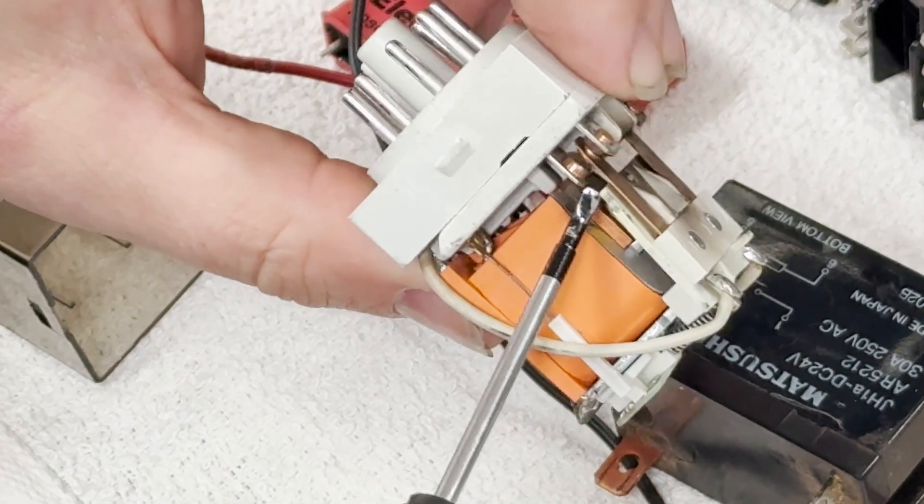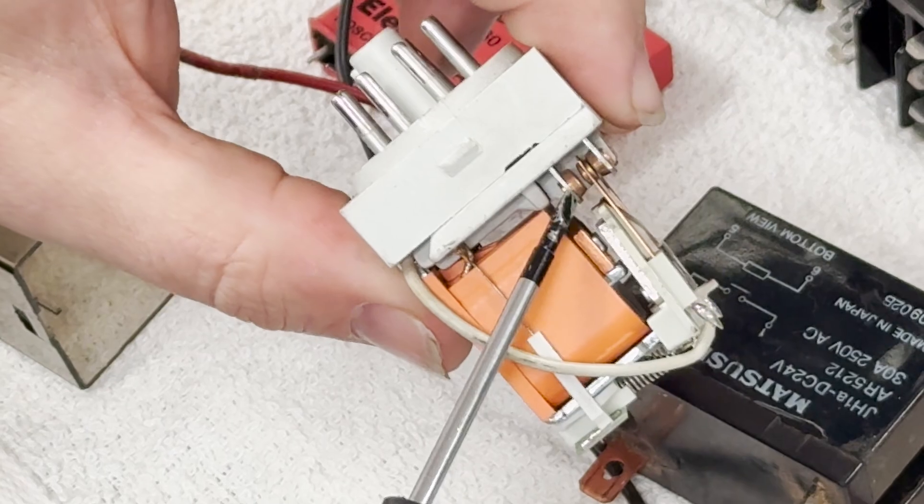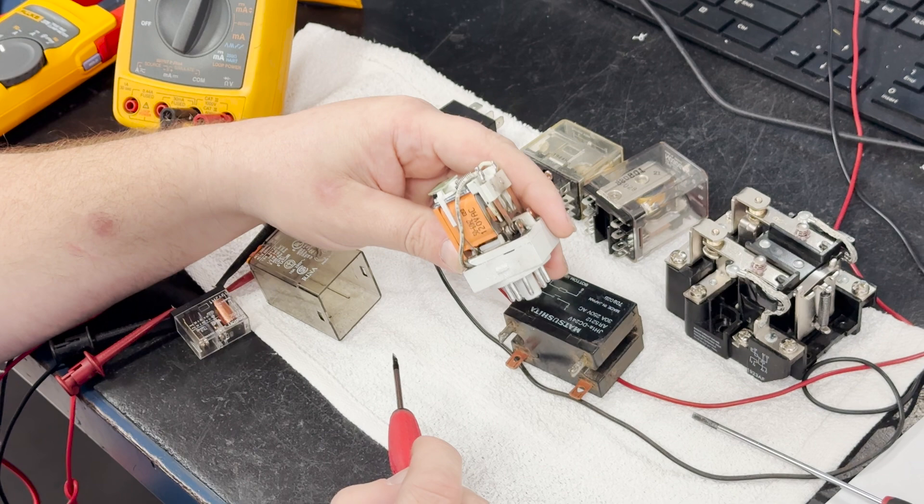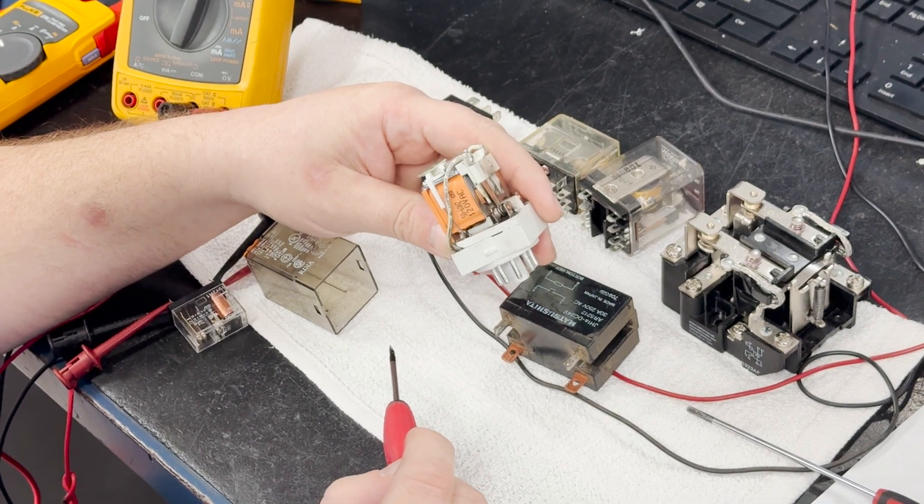So likely this side of the relay is okay and then this side of the relay is what has failed. So this is a good example of the type of common failure that relays undergo after years of use in normal wear and tear.